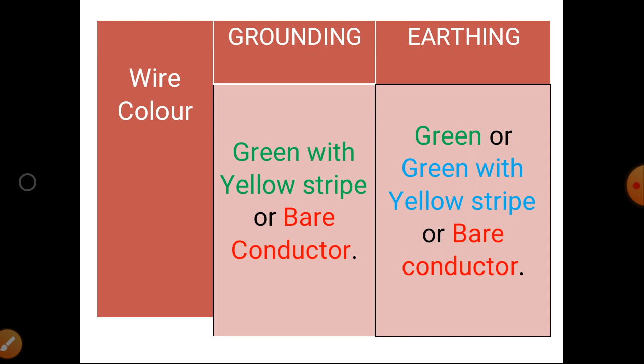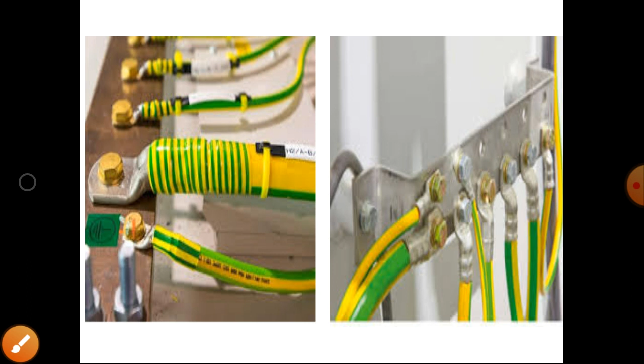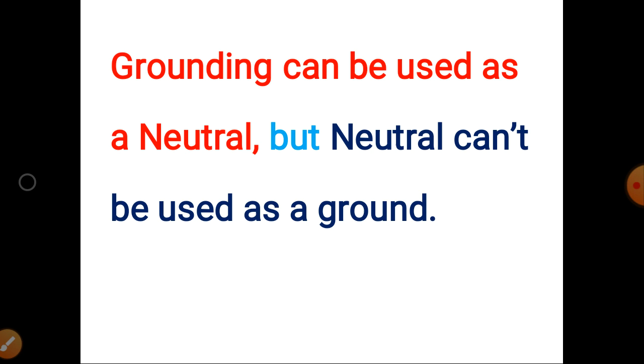See this diagram. Here they are using the green wire with a yellow strip, right? So all the ground wires are normally green color with yellow strip. So this is the color of the wire used for grounding and earthing purpose. Okay, so the main point is, already I said that the ground will act as the neutral, that is a return path, but the neutral cannot be used as a ground, right? So this is a very important one. Already I said that under abnormal conditions the ground will act as a neutral, but the neutral cannot be used as a ground.